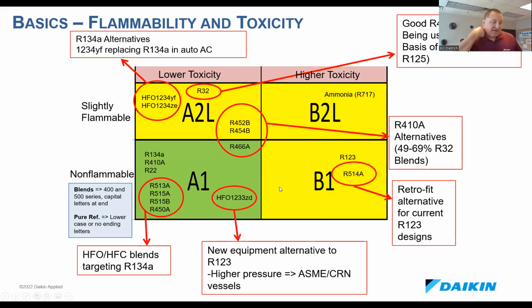And then one of the more interesting compounds that's come out is the HFO 1233ZD. This is one of the few HFOs that actually falls into the green A1 box, and it's a new equipment alternative to 123. It's considered low pressure, but it's higher pressure than 134 or 123, so the heat exchangers have to be designed above 15 PSI. ASME exempts any shells at 15 PSI and below from having any type of code stamps on them. HFO 1233 will have a design working pressure of about 45 or 50 PSI. It will still operate in a vacuum in the evaporator when it's running, but the shells will have ASME code stamps on them. So it's an interesting product, and given its A1 category, it's coming to the market from a number of manufacturers right now.